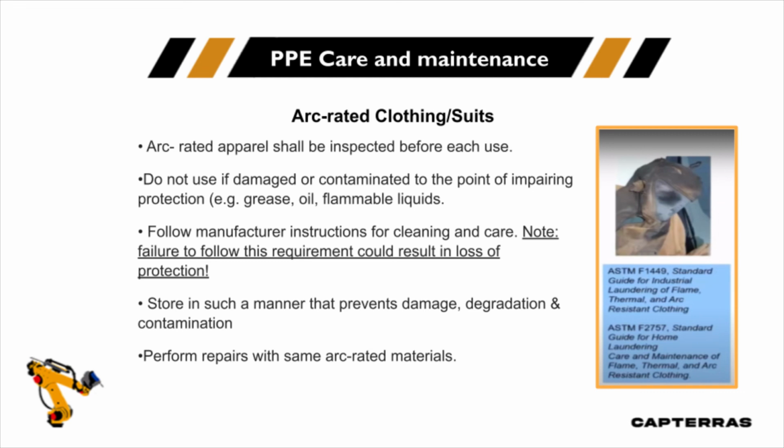for industrial laundering. Make sure your industrial launderer is following the right laundering practices, and this is a very important thing as well. If folks are taking the garments home and laundering them, and it's a treated cotton product, let's say a cotton nylon blend, in as little as 8 to 10 launderings, they can seriously degrade the treatment. A lot of fabrics say right on the garment, do not bleach. Well, if I think do not bleach, I'm thinking of pouring a can of bleach in. I'm not thinking of whiteners and brighteners, sodium hypochlorite or hydrogen peroxide in, let's say, OxyClean or other products that are actually a form of bleach, but don't say bleach right on there. They say whiteners and brighteners.